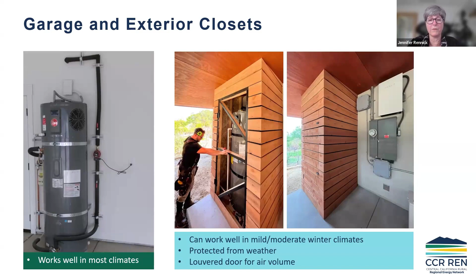It basically looks at that outdoor temperature and says, okay, this unit's going to go into electric resistance heating mode for part of the winter, but then come summer, it's so hot outside that tank of hot water is going to stay plenty warm, so the compressor hardly has to run. So sometimes it's a wash, but better than that on the performance side, when I played with the sample houses and really looked at it, a total indoor location was the best, and having the air come from indoors and exhaust into the indoors was the best.